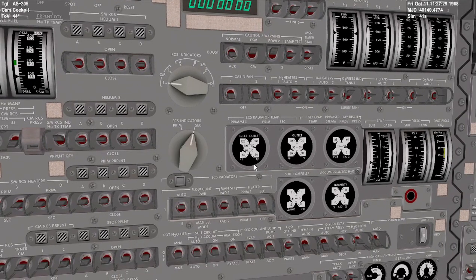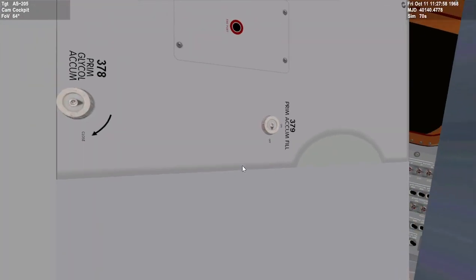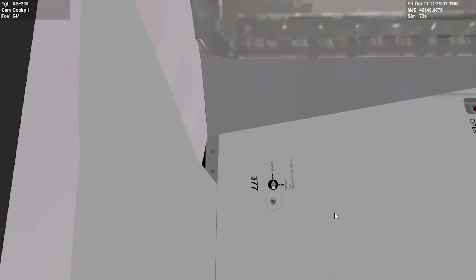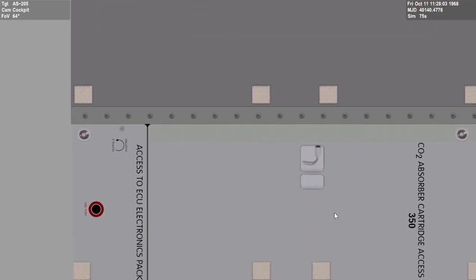Flip over to secondary, switch on AC1 pump, and switch on down to AC2 and verify that the glycol discharge pressure is still holding. Good. Set the secondary coolant loop pump off. You can see it slowly spin down now. Switch back to primary, and you can bypass the secondary glycol to radiators.